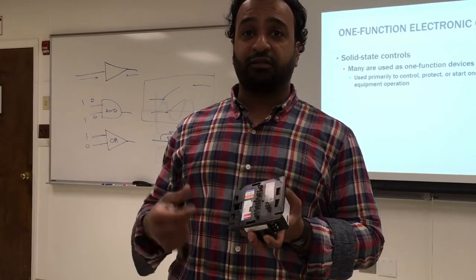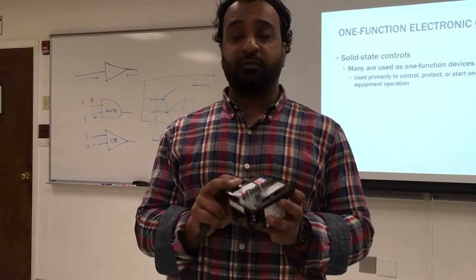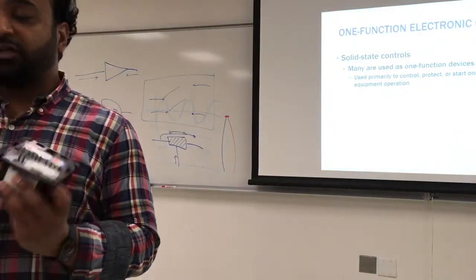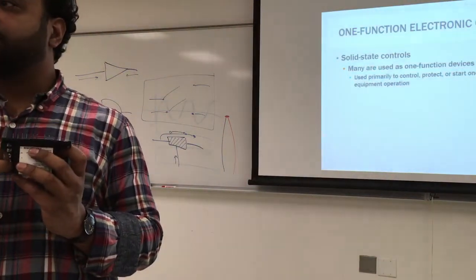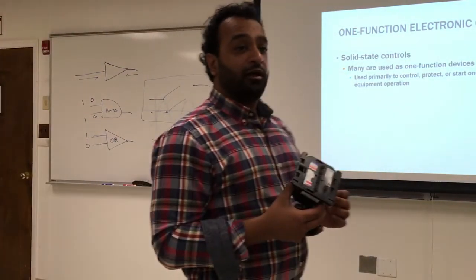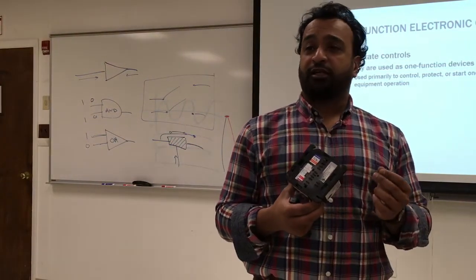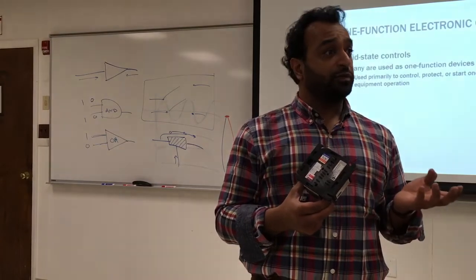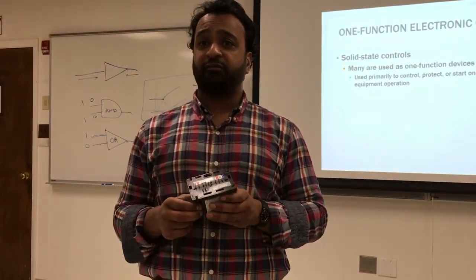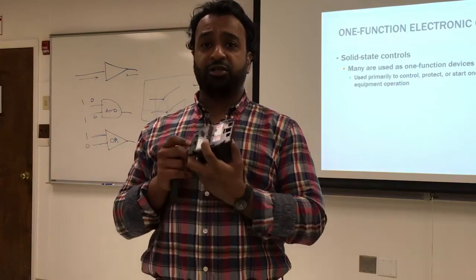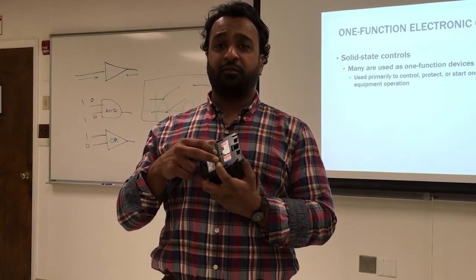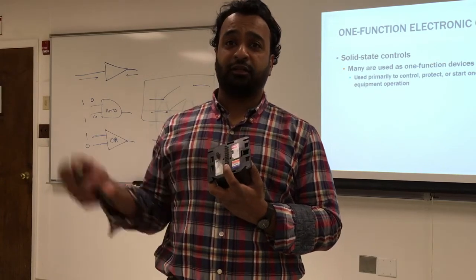Dark or light, different resistance, that's an input. And do I need heat? The thermostat has a connection here. You connect the thermostat, so the thermostat says we need heat. The FF terminals connected to the CAD cell will tell you it's dark, so we need some fire. We turn on the fire. How do we turn on the fire? First of all, I will turn on the ignition and the motor together. Those are connected in parallel. At this point, they turn on.